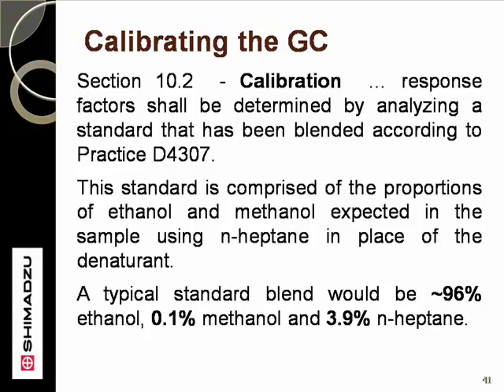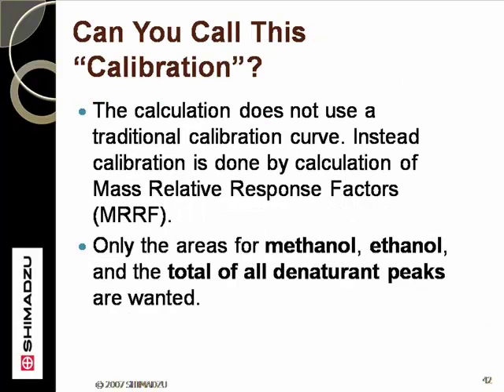The method makes a stipulation that the user can use typical MRRF values if they do not want to measure these values specific to their instrument. However, the typical MRRF values do not seem to match well with the performance of current GC hardware. The method does not use traditional calibration practices with a set of standards to create a standard curve; instead, it uses an internal comparison where ratios of peak areas are used to calculate content. The MRRF values are critical to getting a more accurate result.